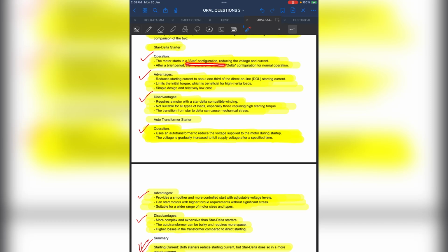And why do we give the star configuration first? To reduce the starting current. So that's why we first provide the star configuration, and after that we switch over to delta to give the full voltage to run the motor. Okay, so what are the advantages of using this? The reduced starting current, about 1/3 of the direct online starting current. Let's suppose you are using a DOL starter. With a DOL starter, when you start a motor it will take a very high current, like 5 or 7 times the rated current of the motor. So we are reducing the starting current to about 1/3 of the DOL starting current.